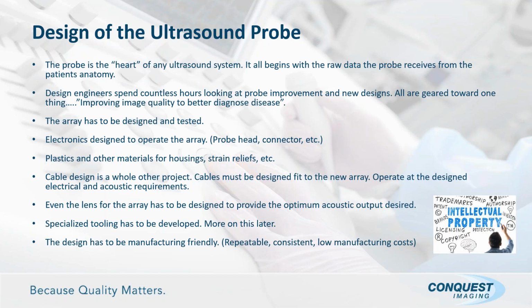So where do the OEMs start with the design of a probe? Well, for one, and I know I've given talks on this before, the probe really is what I consider the heart of the ultrasound system. It's the one that's receiving data back from the patient, and the system is forming that into the images that we see, Doppler, etc. And it really begins right there, because if we input bad data, the machine is just going to put out whatever it sees. That's why I think so much engineering effort and R&D is put into the probe by the various OEMs, because it really starts with that. And the system is there to support the probe, in my opinion.